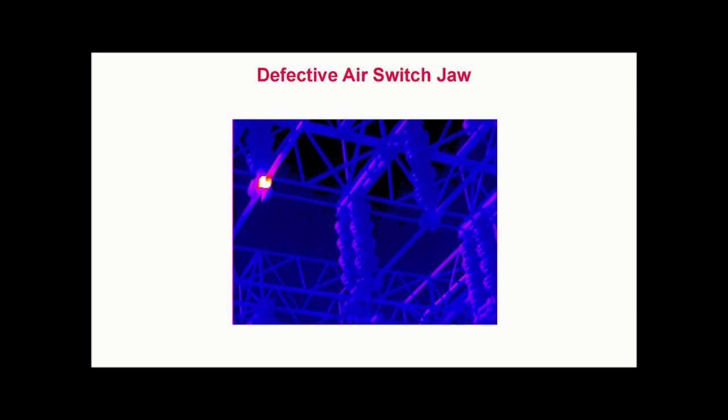This thermal pattern is typical of a loose or deteriorated connection due to the localized heating at the junction of the stationary and movable contacts. Although under the same load, neither of the adjacent switch poles, which are represented in blue, exhibit this type of localized heating.